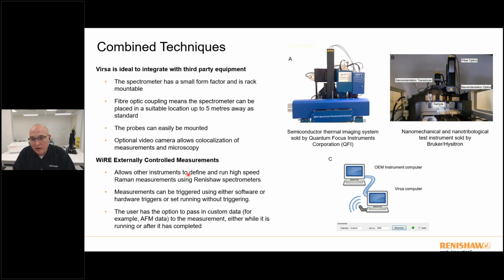And then we also have an option of being able to either simply install the Renishaw control software on those third-party instruments, or we have the ability to have two completely separate PCs and use something called external controlled measurements, which gives us the ability to use JavaScript RPC to communicate between these two PCs when to collect data. And the advantage there is as we are collecting and controlling the Raman system with this third-party instrument, we can also be shuttling that data into the Renishaw WiRE software, and that way it's really easy to correlate all that information.